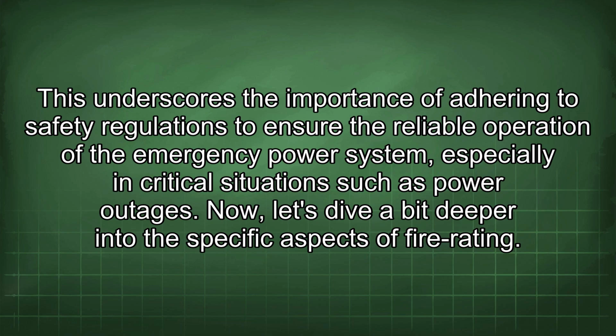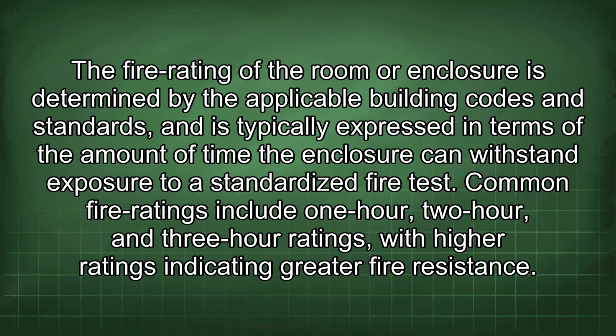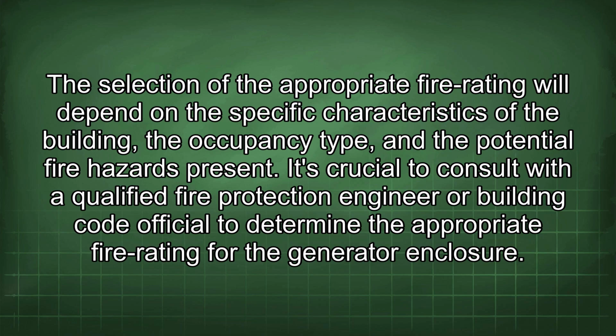Now, let's dive a bit deeper into the specific aspects of fire rating. The fire rating of the room or enclosure is determined by the applicable building codes and standards, and is typically expressed in terms of the amount of time the enclosure can withstand exposure to a standardized fire test. Common fire ratings include 1-hour, 2-hour, and 3-hour ratings, with higher ratings indicating greater fire resistance. The selection of the appropriate fire rating will depend on the specific characteristics of the building, the occupancy type, and the potential fire hazards present.